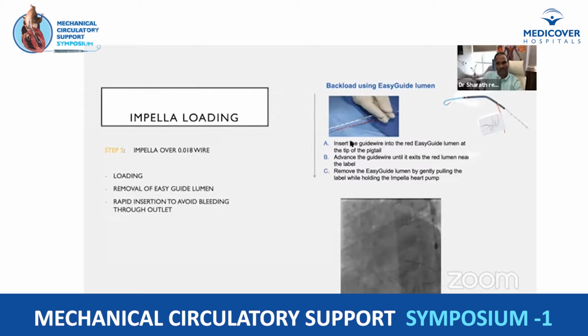So for Impella loading, there is an easy guide lumen which is present within the Impella. You can see this, the red one is the easy guide lumen, which comes out of your outflow. So this is the Impella outflow, which stays in the aorta. So this is for easy wiring, and this is very, very important. Once you have wired, you have to remove this easy guide lumen. So thread the Impella over the wire, and then remove this easy guide lumen. Otherwise, if it goes in and you start the Impella, you will end up with the Impella stuck with this easy guide lumen. So load it, remove the easy guide lumen, and then insert into the sheath.